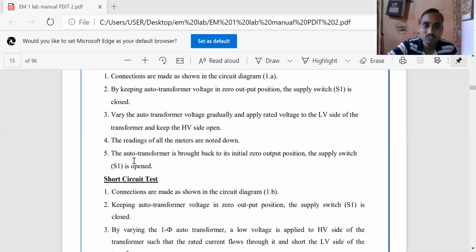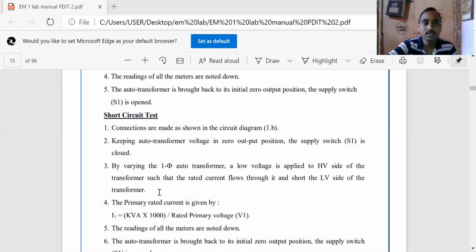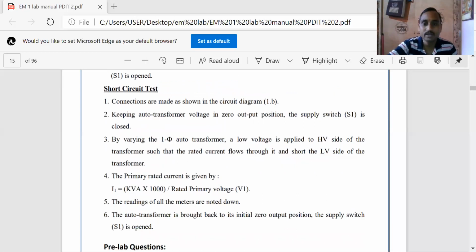Then the auto transformer is brought back to the initial zero output position. Once it is over, you come back to the zero position and the switch is opened. Similarly, for the short circuit test, connections are made as per the circuit diagram, and you vary the single phase auto transformer. Low voltage is applied to the HV side of the transformer such that rated current flows through it, with the LV side of the transformer short circuited.